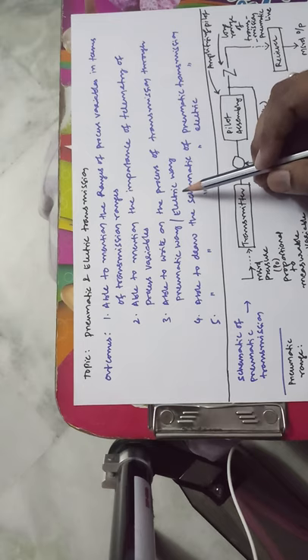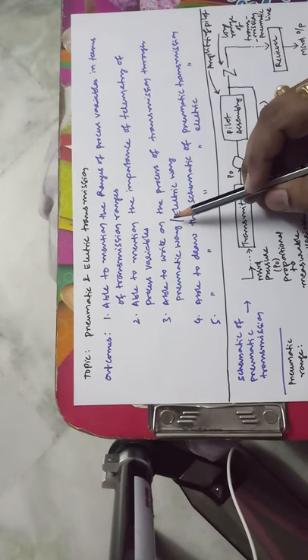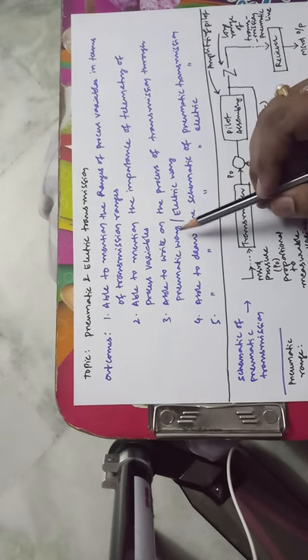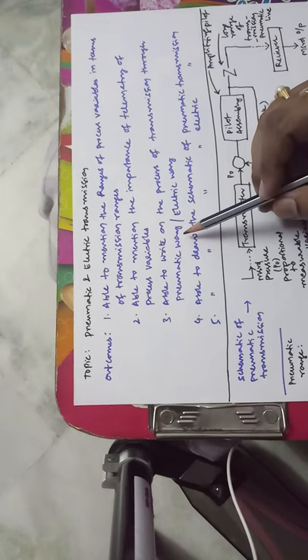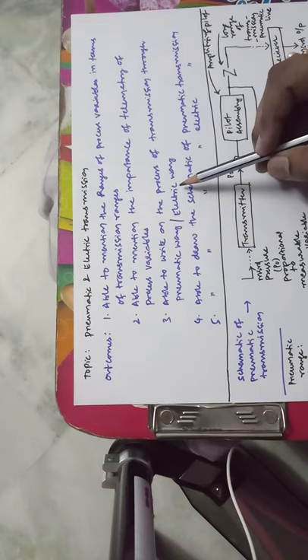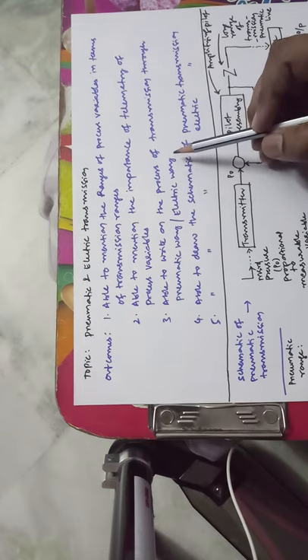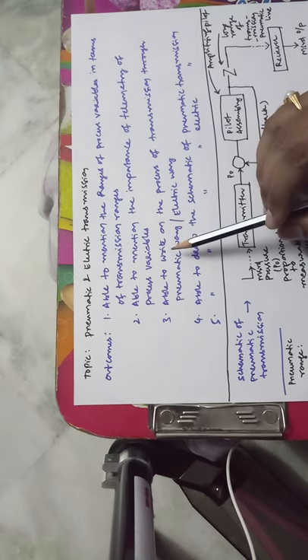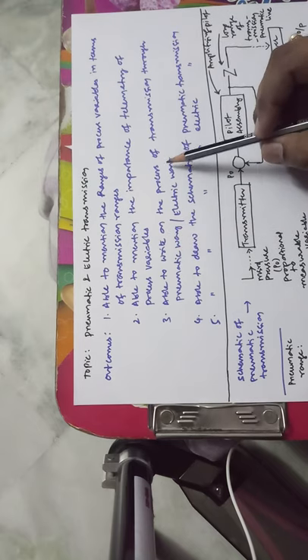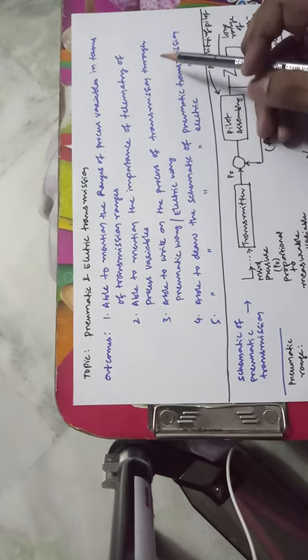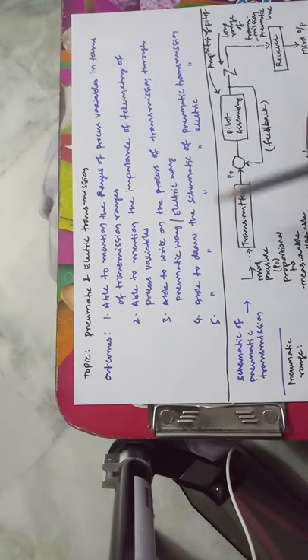Most process variables will be transmitted either in pneumatic pressure in the range of 3 to 15 PSI, or through electrical transmission using 0 to 5 volts of voltage, or 4 to 20 milliamps of current. The student will be able to write on the process of transmission through pneumatic or electrical means.